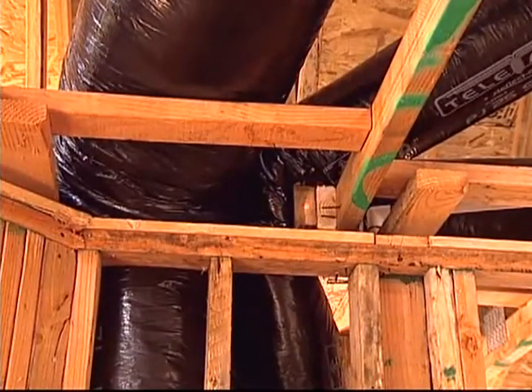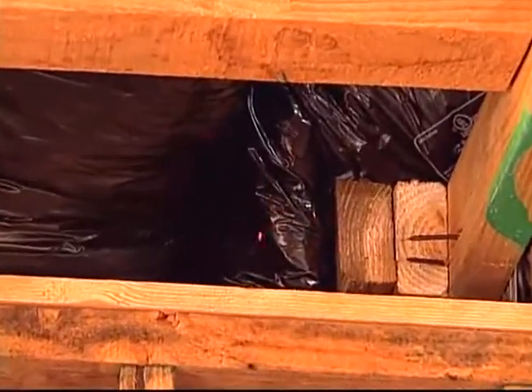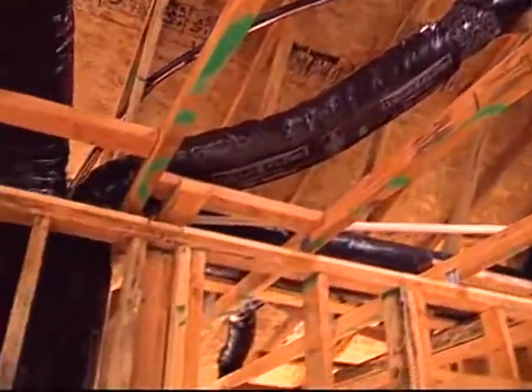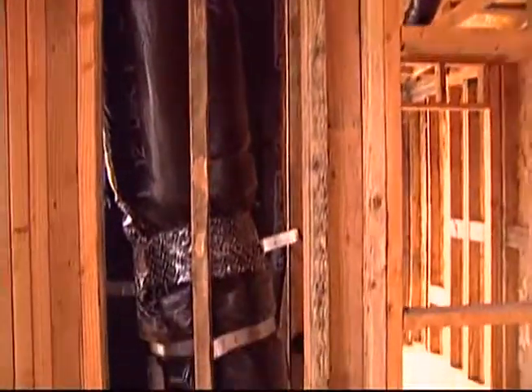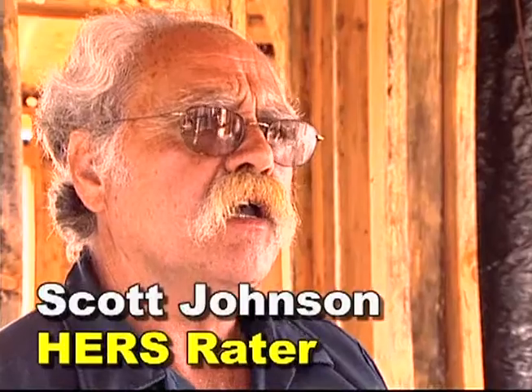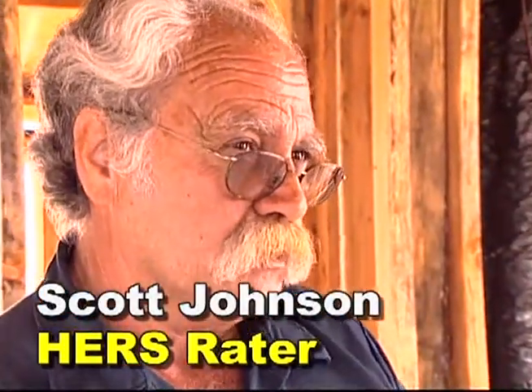What other things did you find here? I found other restrictions — there's a restricted return duct, and there's a problem with a shaft where many ducts run inside of it. They get all compressed; the shaft is just not big enough to accommodate the ducts. Any other problems? The equipment's leaking air, and there's actually this unit leaking air too. We'll see it on a smoke test.